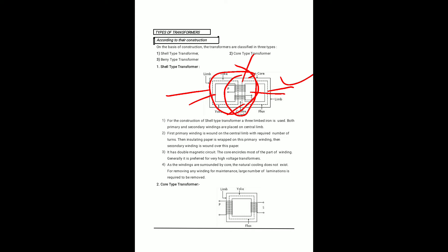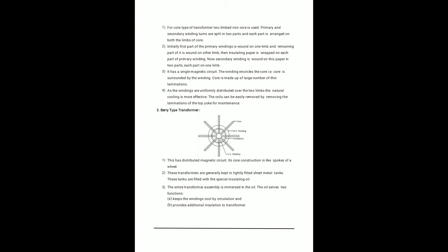In the core type transformer, two limbs and a core are used — there are two windows with two limbs. The primary and secondary winding turns are split into two parts, with each part arranged on both limbs of the core. The first part of the primary winding is wound on one limb and the remaining part is wound on the other limb.